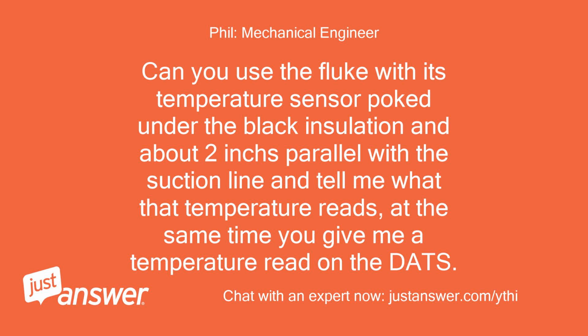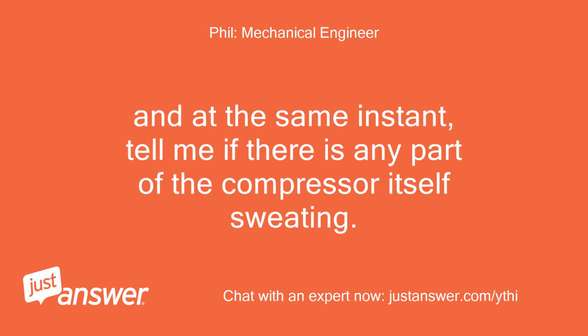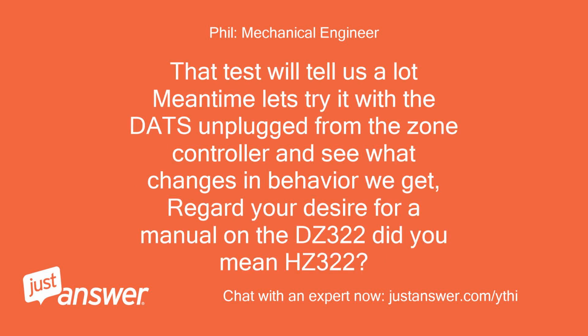Can you use the Fluke with its temperature sensor poked under the black insulation and about 2 inches parallel with the suction line and tell me what that temperature reads, at the same time you give me a temperature read on the DATS? And at the same instant, tell me if there is any part of the compressor itself sweating. That test will tell us a lot. Meantime, let's try it with the DATS unplugged from the zone controller and see what changes in behavior we get.